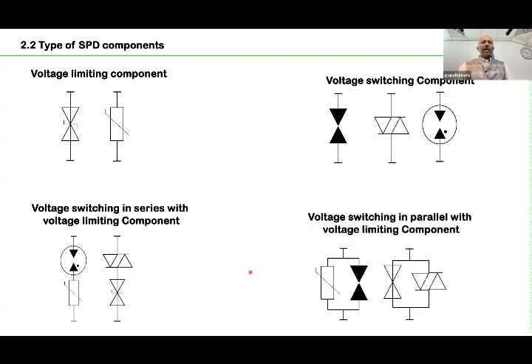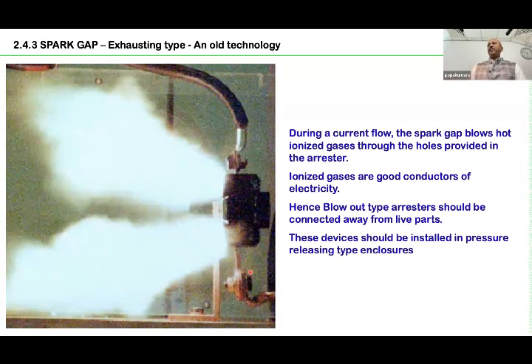Similarly, there can be several types of SPDs: only MOV, only GD tube, sometimes a series-parallel combination of GD tubes, MOVs and so on. It depends on the design of that particular SPD. One of the SPDs which was used long back was the spark gap. Spark gap, as the name tells. So there is a gap, and once the potential crosses the limit, it creates an arcing.